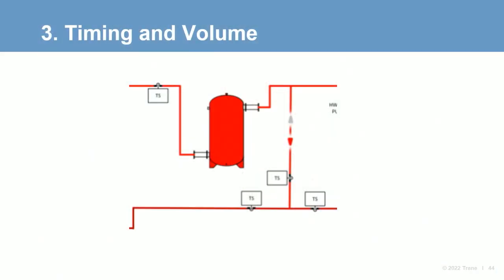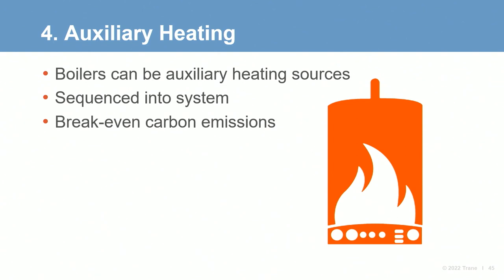Third is the timing and volume. Some heat pumps have timers that limit defrost mode duration, which can be used to estimate the transient impact on heating capacity. Adding system volume to counter this is a good system choice. With more loop time, defrost will have a lower impact on the distribution systems, smoothing out system operation and temperature delivery. Rick will cover this in more detail shortly. Lastly, auxiliary heating sources such as boilers can be used to satisfy the heating load or supplement plant heating capacity in situations where the heat pump heating capacity is limited. Auxiliary heating sources can be sequenced into the system at the break-even carbon emissions point, which Charlie will discuss.